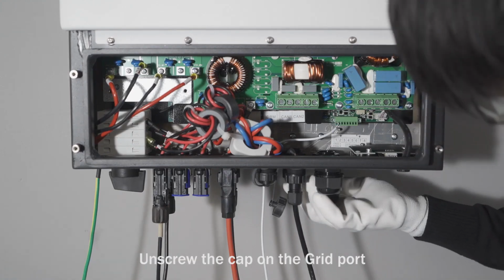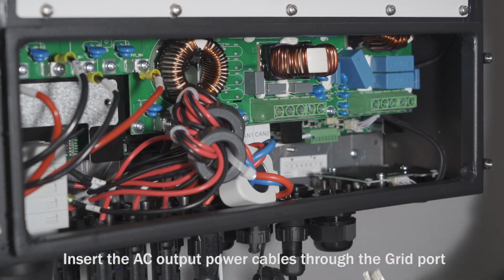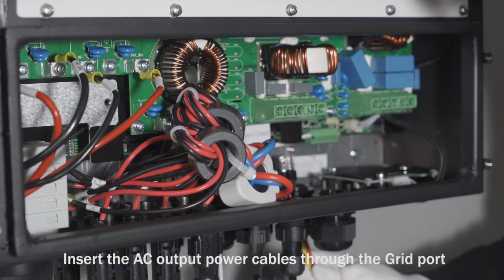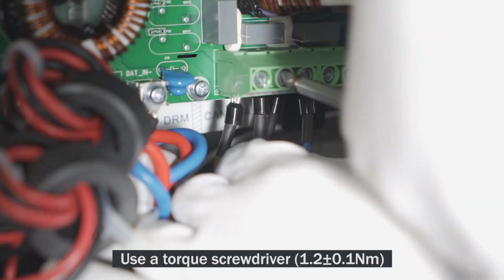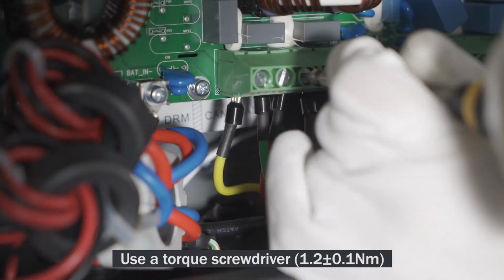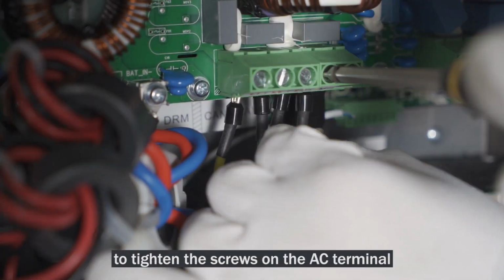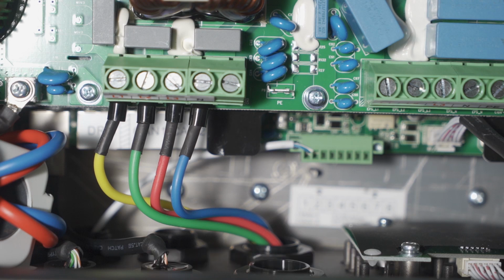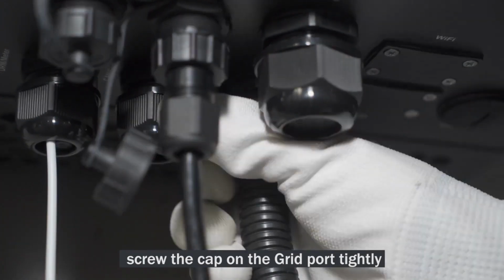Unscrew the cap on the grid port. Insert the AC output power cables through the grid port. Use a torque screwdriver to tighten the screws on the AC terminal. Screw the cap on the grid port tightly.